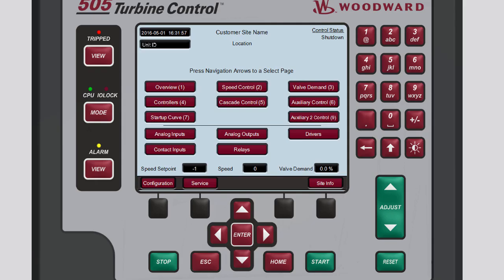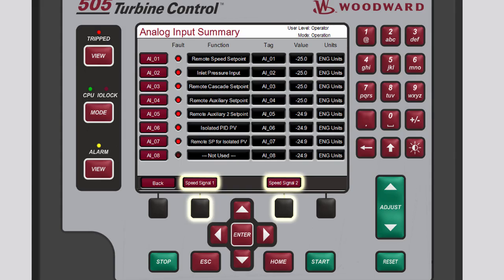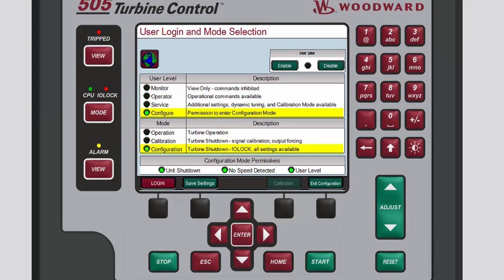Let's examine one of the input screens. Select Analog Inputs to open the Analog Input Summary screen. On this screen, you can see what values are available for each channel. You can also access the two speed input signals from this screen by pressing the black function key below the desired speed signal number. To set up the input-output channels, place the unit into Configuration Mode, and then select and change each channel for the different input-output types.